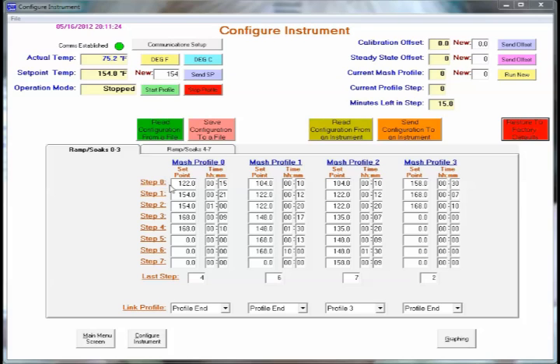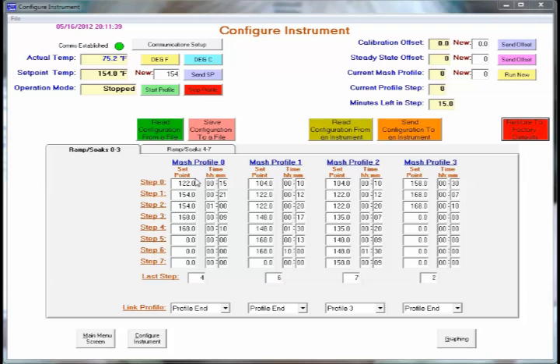And if you notice you start with a rest and then you have a ramp and a soak. A ramp and a soak. And you simply just do your calculation based on your ramp rate. You subtract the two temperatures and divide it by the ramp rate. And that's your time that you enter. And the controller will follow that.